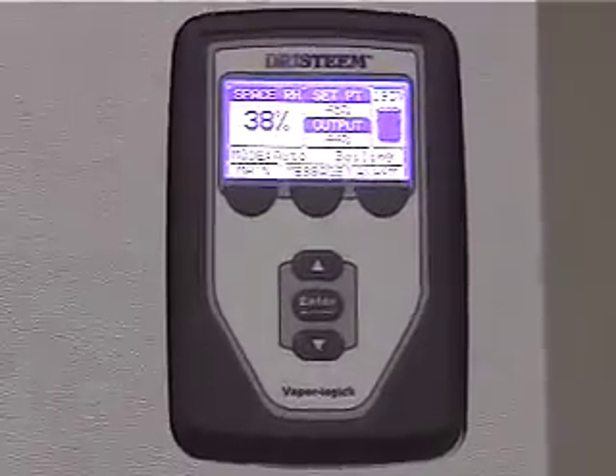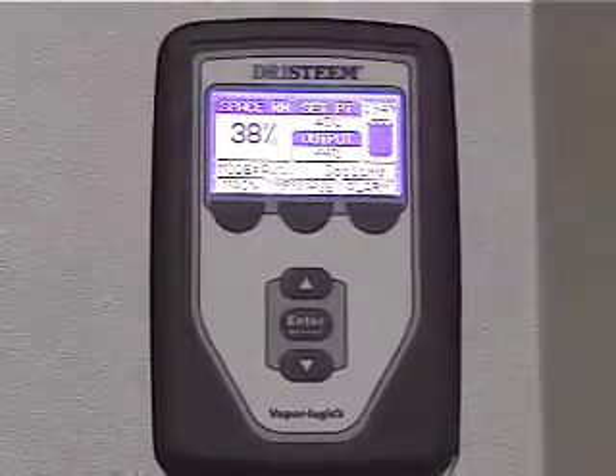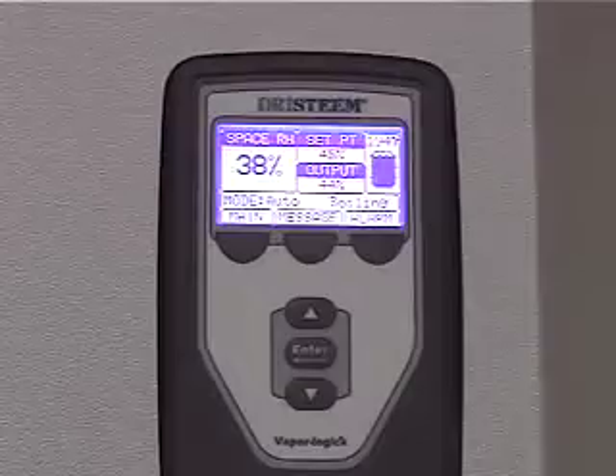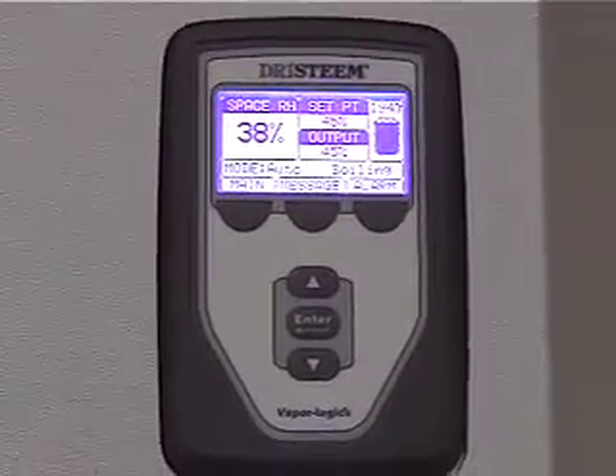So it's saying even though we changed our set point to 45%, we're only at 38% in this room. 44% will still catch up. We still don't need even 100%. But remember, it's a contactor, so it's either all or nothing. We actually have these in natural gas, where I can give you an output from 10% to 100% output steam, and anything in between.